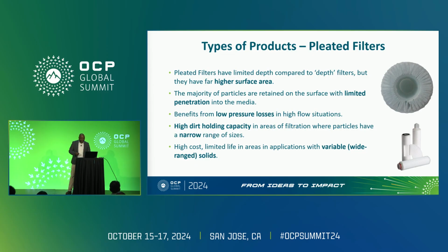The next product that you would commonly use within the filter housings in liquid cooling systems would be pleated filters. Now, this is a brilliant piece of technology in the right setup, and context is really king when you're dealing with this filter. If you have a wide particle size distribution, forget about it. This isn't the product because you'll get clogged up very quickly.